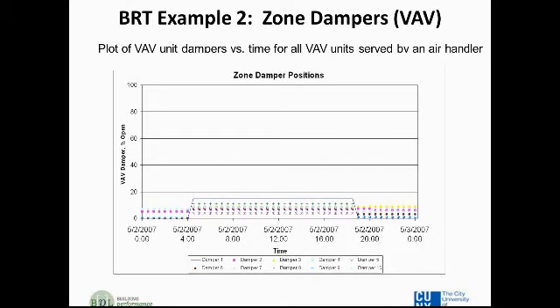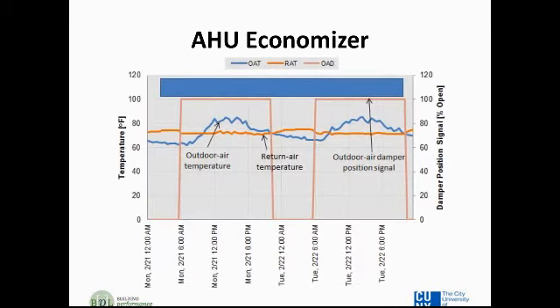And in a situation like this, obviously, you've got an opportunity. If you've got a VFD on the motor that drives the fan in your air handler, you can use it. You can back off. Knowing that the power the fan motor consumes is proportional to the cube of the fan speed, if you can cut that fan speed by half, you've cut the power consumption by a factor of 8. So tremendous savings opportunities here.